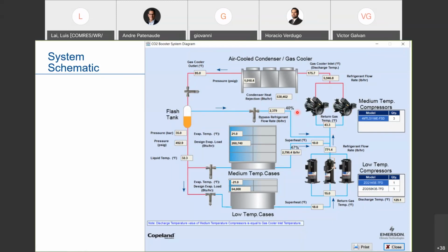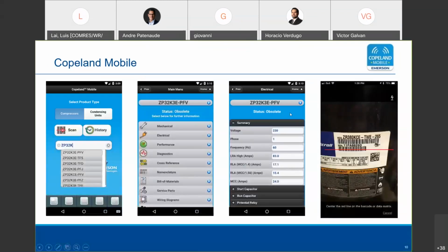And I pointed that out because last training session, I talked about high ambient strategies, adiabatic gas cooling, parallel compression, subcooling, liquid and gas ejectors, all of that. That's all done in order to reduce this inefficient bypass of mass flow. That's what all of those strategies are about. If you can reduce this inefficient mass flow bypass, then your entire system becomes more efficient. You add complexity, but you increase efficiency. And that's a key component of understanding why a basic CO2 transcritical system is not that efficient at high ambient. If it was 95 degrees gas cooler out, that would be a higher percentage number. I just wanted to make sure I pointed that out. And the software shows that.